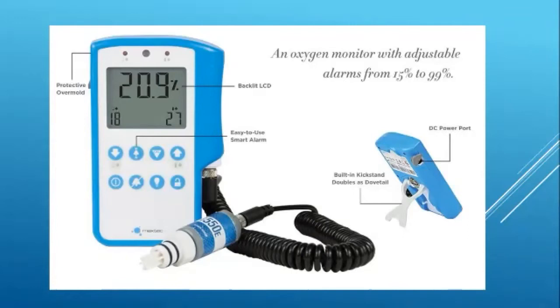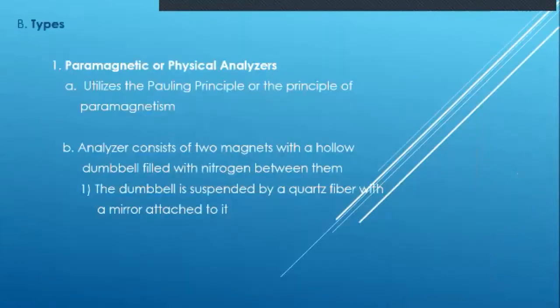And then you would put it in the stream of pure oxygen and make sure it says what? 100. 100%. Okay? And so that's how you analyze. But it's going to be a little bit more tricky how you analyze, but we'll learn that in a minute. So this is one example of an oxygen analyzer. Okay, here go the types.